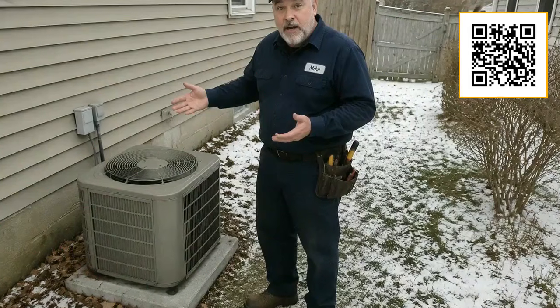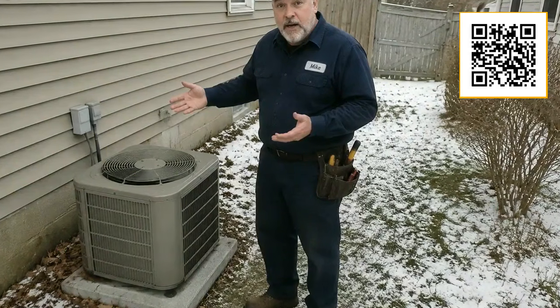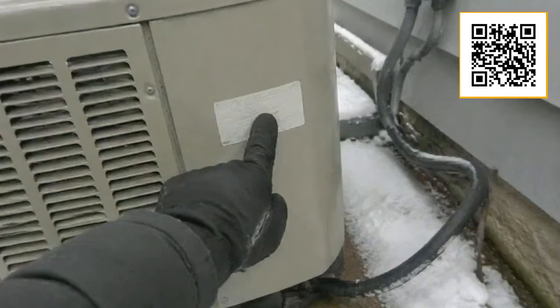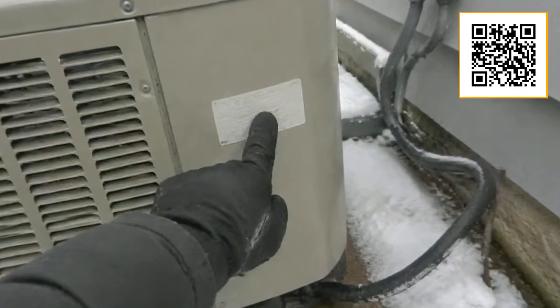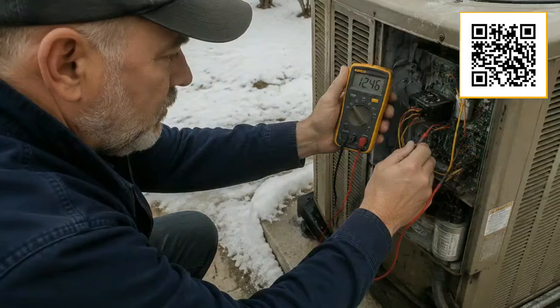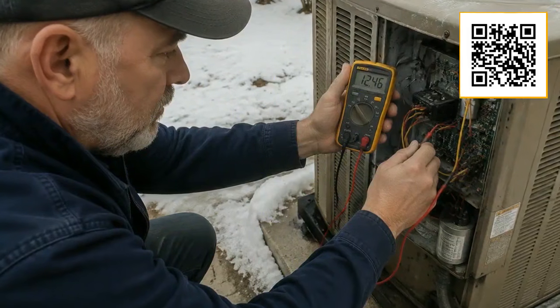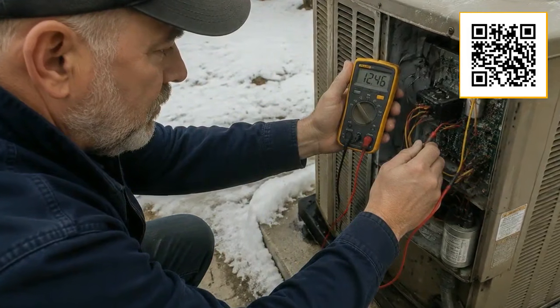If you live somewhere with hard winters and you are considering a heat pump, make sure you are choosing a model rated for cold climates and that your installer understands how to set up the defrost controls correctly.